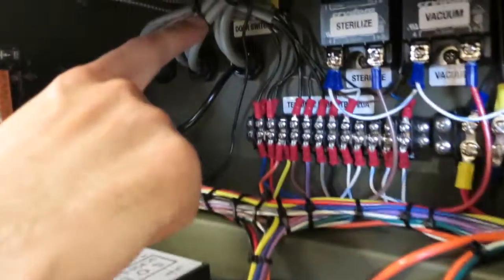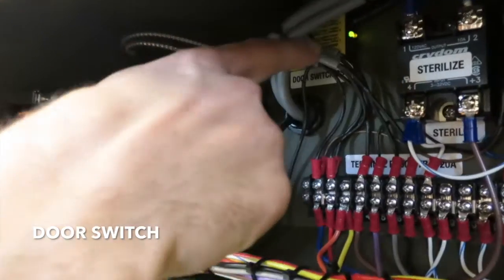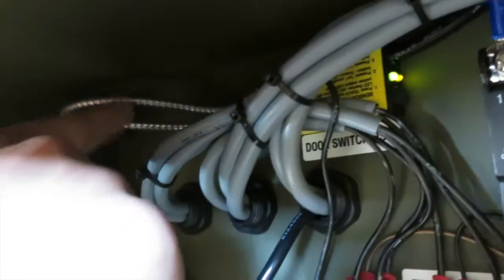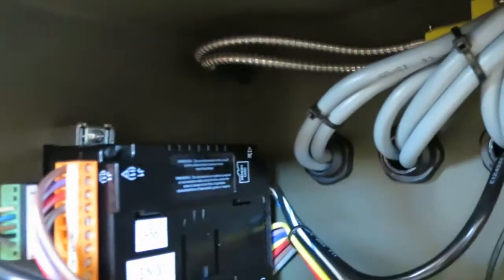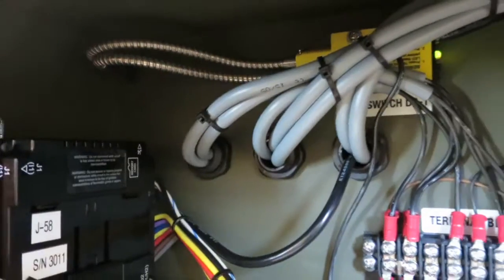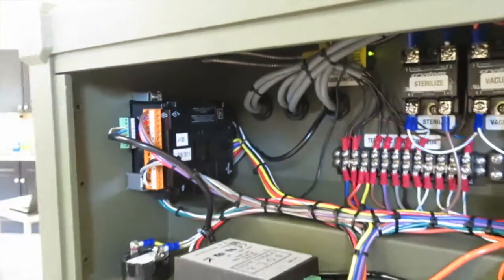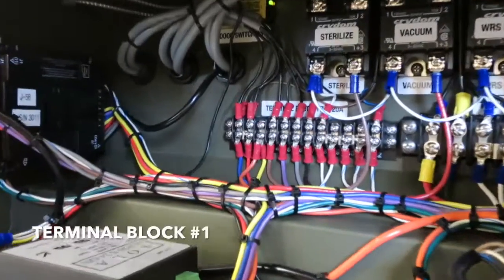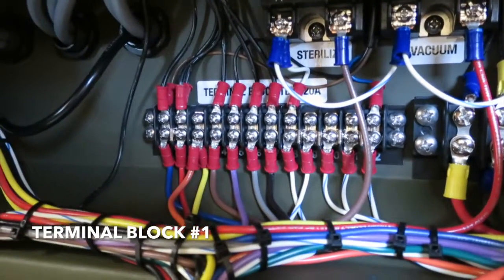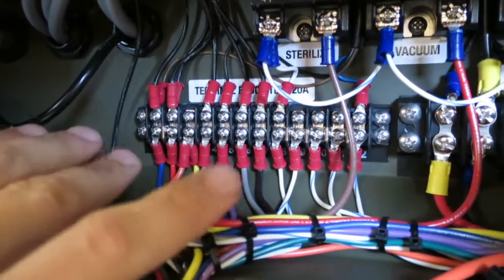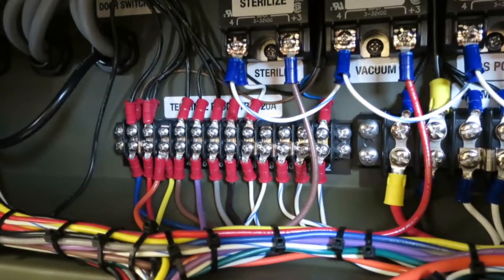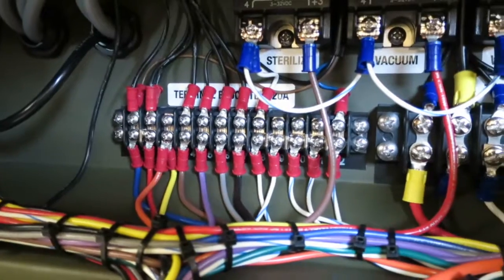Alright, up here to the left we have the door switch sensor. It's this yellow piece with that green LED light on. You'll see these two metal clad cables coming in. That's to protect the fiber optics inside, just to make it pretty durable. So you'll notice there's a pretty big bend there just to protect and not damage those fiber optics. And the wiring comes down and connects to the terminal board, which is then connected to the PLC. Right here we have terminal block number 1, and a lot of that is the 24 volts and a lot of the connections to the valves and the transmitters throughout the unit. Alright, so that's it for the right side of the sterilizer main unit.